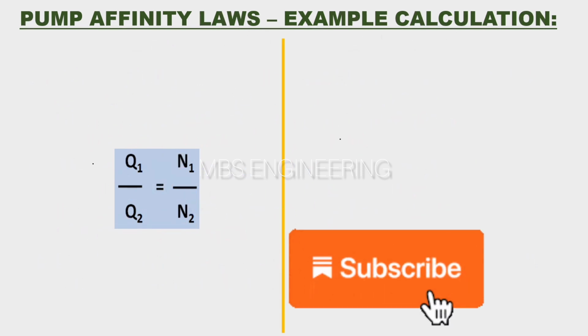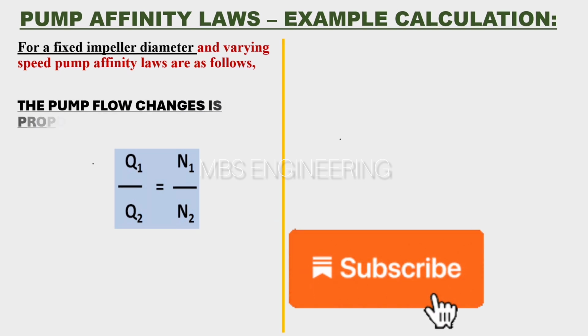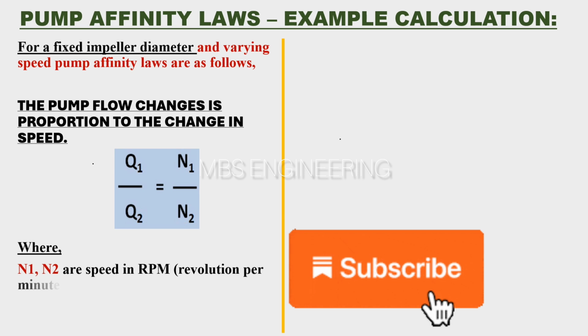Next, we learn about the formula for pump affinity laws and will understand with sample calculations. For a fixed impeller diameter and varying speed, the pump affinity laws are as follows. The first affinity law: the pump flow changes in proportion to the change in speed. The pump flow Q1 divided by Q2 is directly proportional to its speed N1 divided by N2, where N1 and N2 are speeds in RPM, revolutions per minute, and Q1 and Q2 are volumetric flow rates in cubic meters per hour.